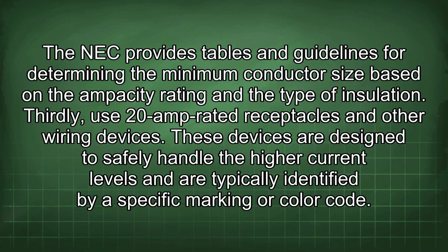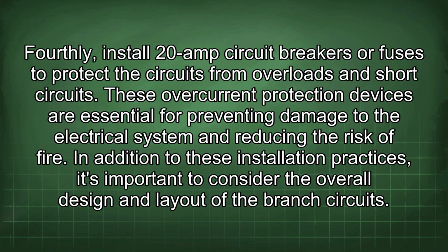These devices are designed to safely handle the higher current levels and are typically identified by a specific marking or color code. Fourthly, install 20 amp circuit breakers or fuses to protect the circuits from overloads and short circuits. These overcurrent protection devices are essential for preventing damage to the electrical system and reducing the risk of fire.